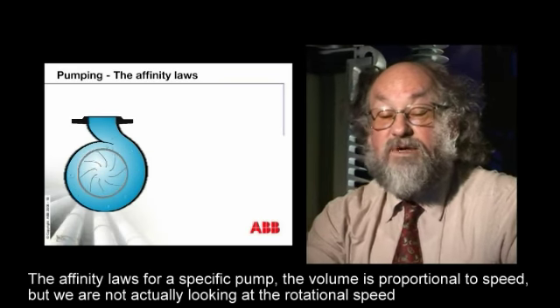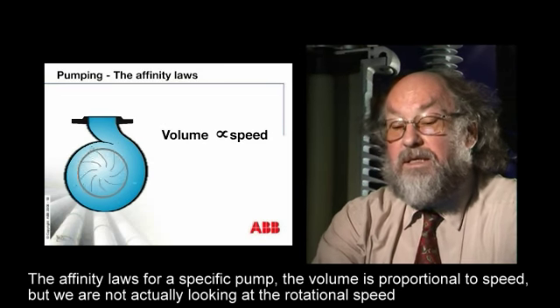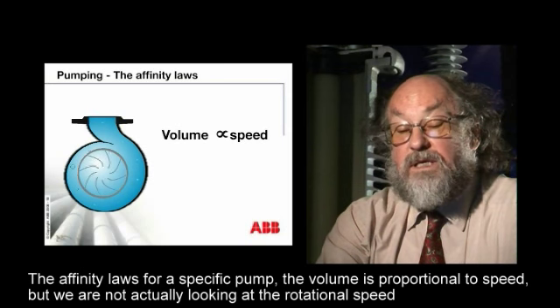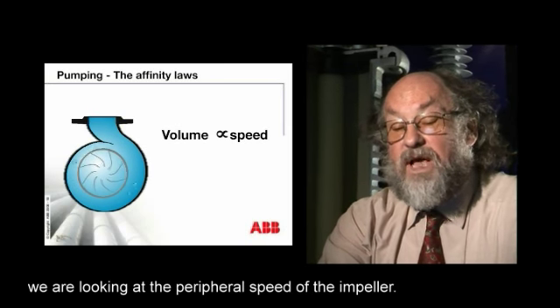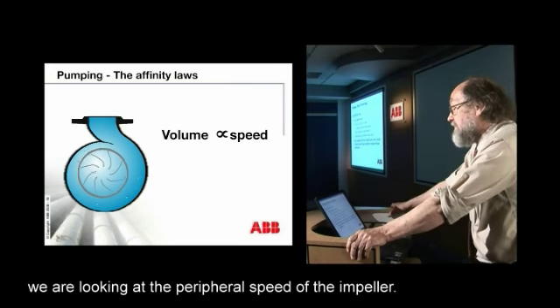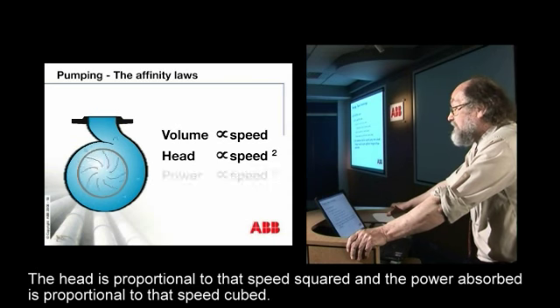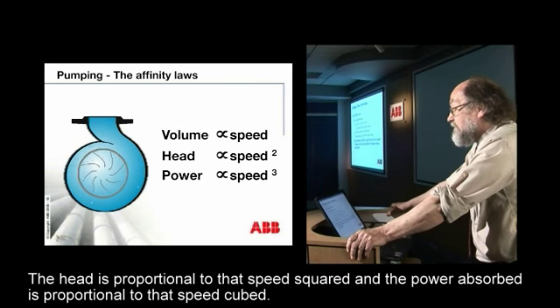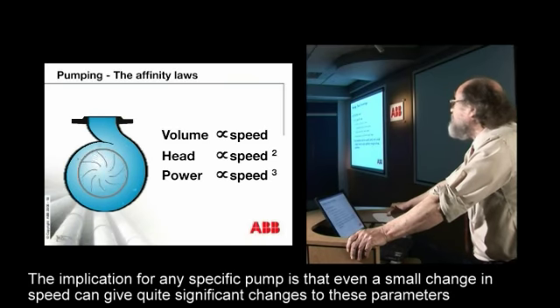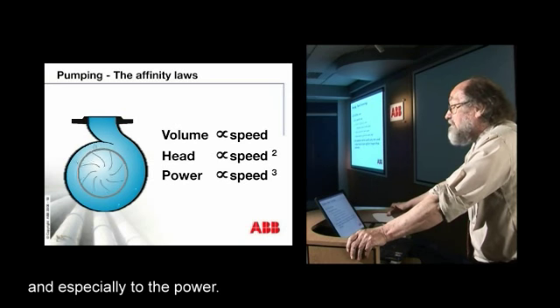The affinity laws for a specific pump state that the volume is proportional to speed — and we're not actually looking at rotational speed, but the peripheral speed of the impeller. The head is proportional to that speed squared, and the power absorbed is proportional to that speed cubed. The implication is that even a small change in speed can give quite significant changes to these parameters, and especially to the power.